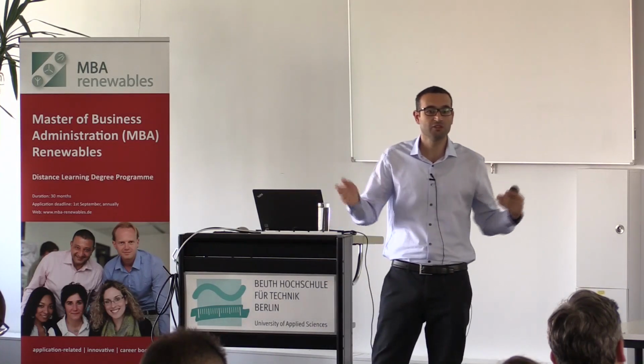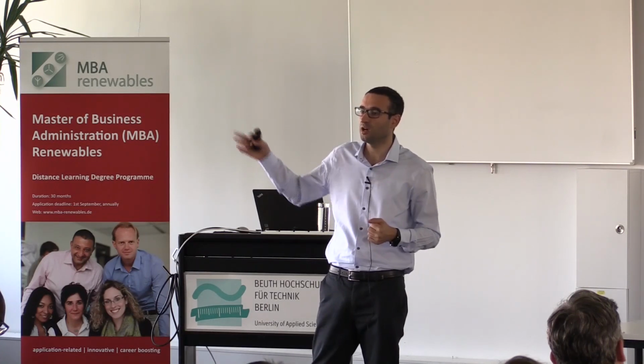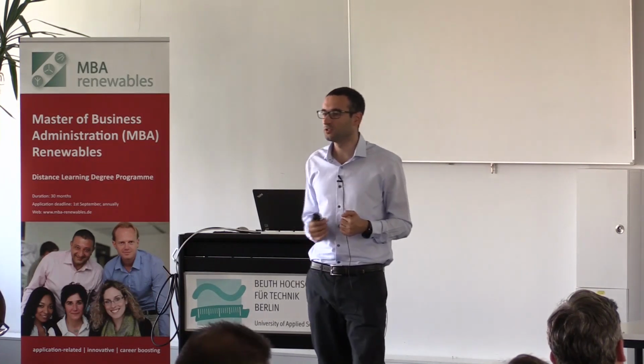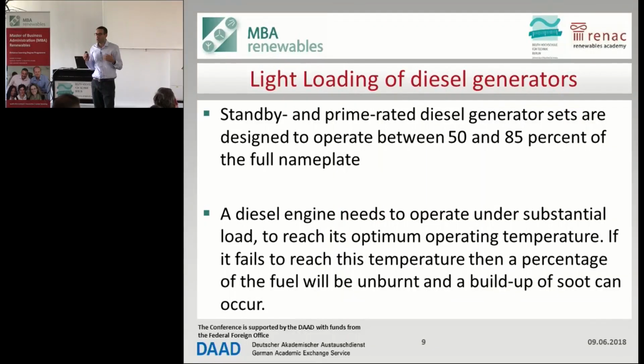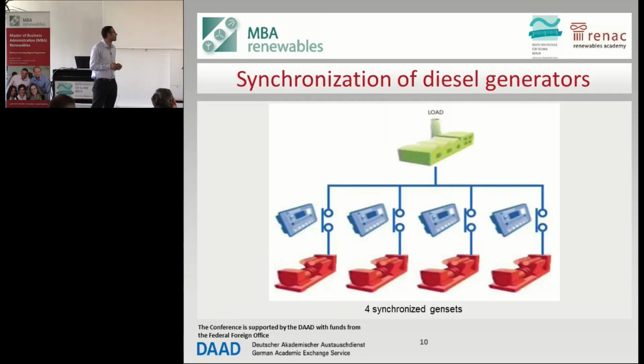So a lot of sludge and a lot of fuel will be running out of it. You will be building sludge at the output, at the exhaust of the diesel generator. This will reduce the lifetime of the diesel generator. It will also increase the burning of fuel and the burning of oil. So light loading is the thing that you want to avoid all the time.